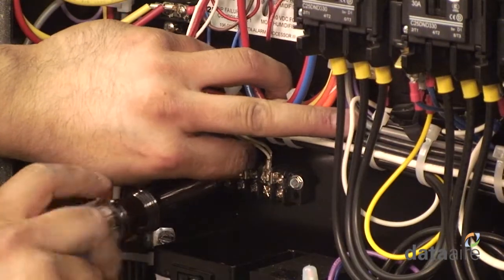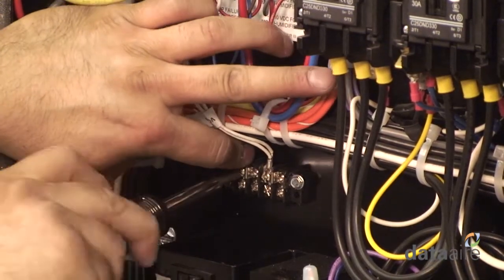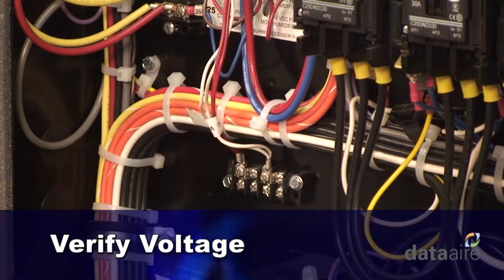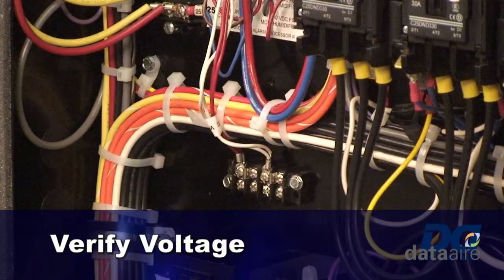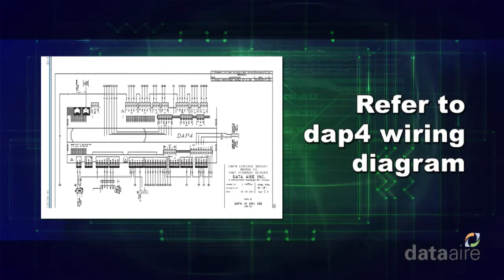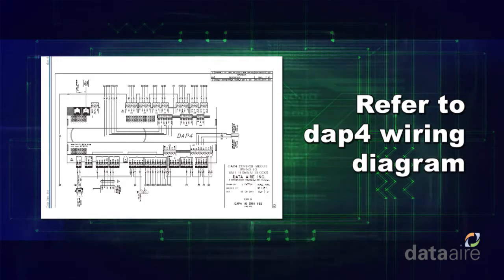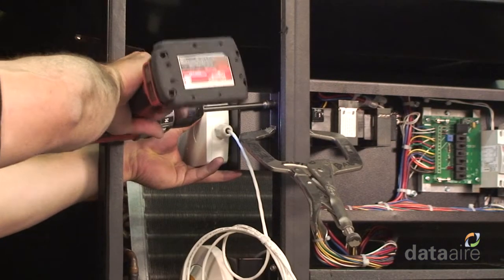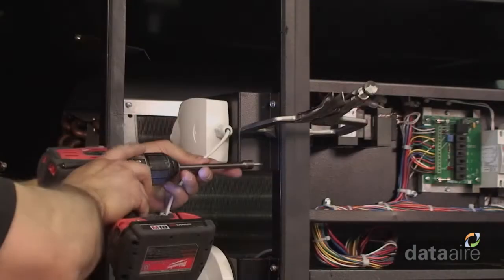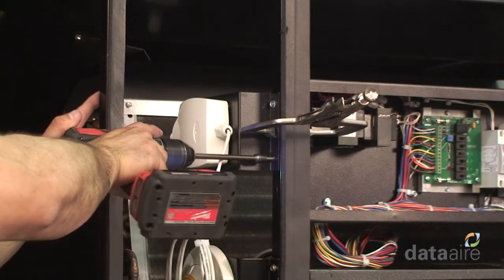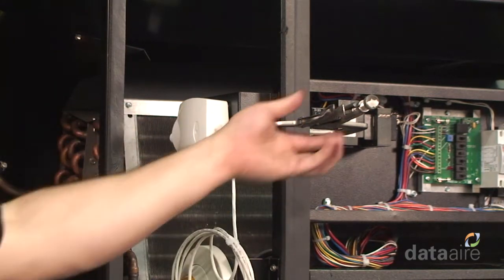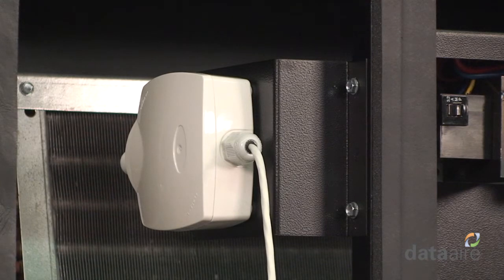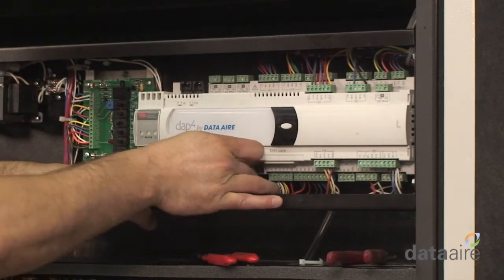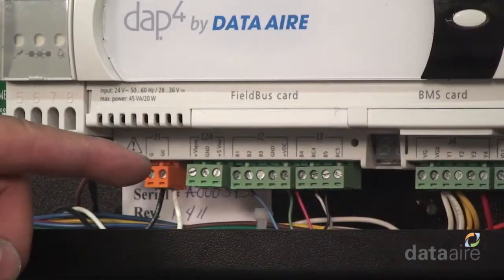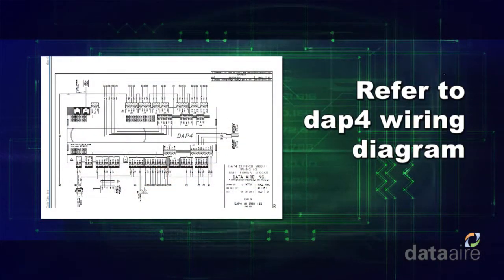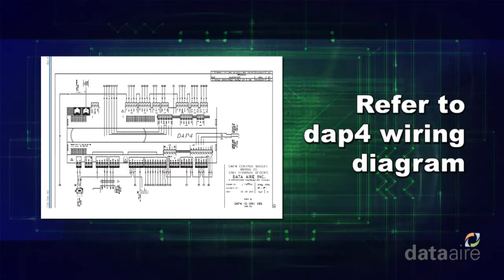Connect the primary side of the isolation transformer of the DAP4 to the top of the fan contactor. Be sure to verify the voltage before making this connection. Please refer to the DAP4 conversion wiring diagram for wiring details. Mount the DAP4 temperature and humidity sensor in the same location where the existing temperature and humidity sensor were located, in the return air section of the unit. Note, the existing sensor mounting bracket may be used. Then connect the temperature and humidity sensor to the J2 and J3 connectors of the DAP4 controller. Again, refer to the DAP4 conversion wiring diagram for all wiring details.